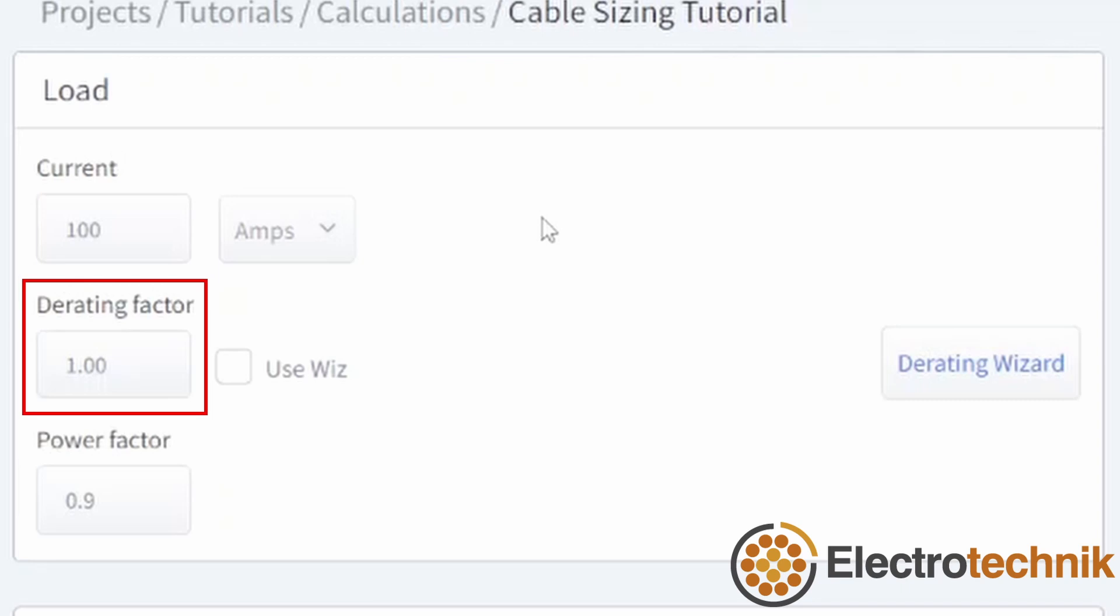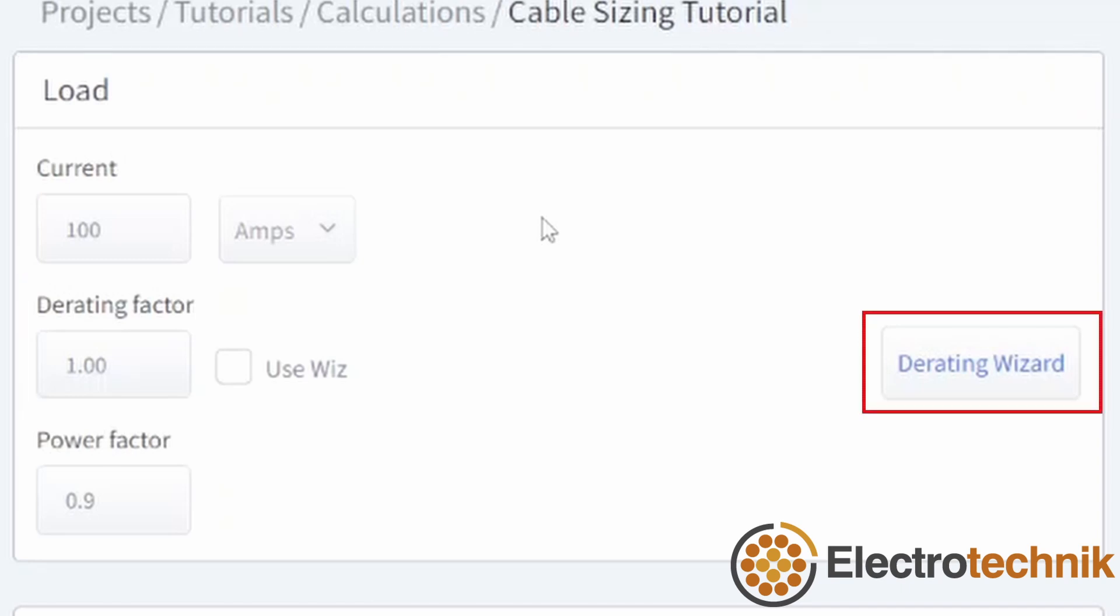A derating factor can be entered and this is multiplied by the standard current rating of the selected cable size. Derating factors are used when your actual installation conditions differ from the standard conditions assumed by the standard. There is a button called derating wizard which opens a window to help you work out the derating factors for your installation. I'll explain this one later.